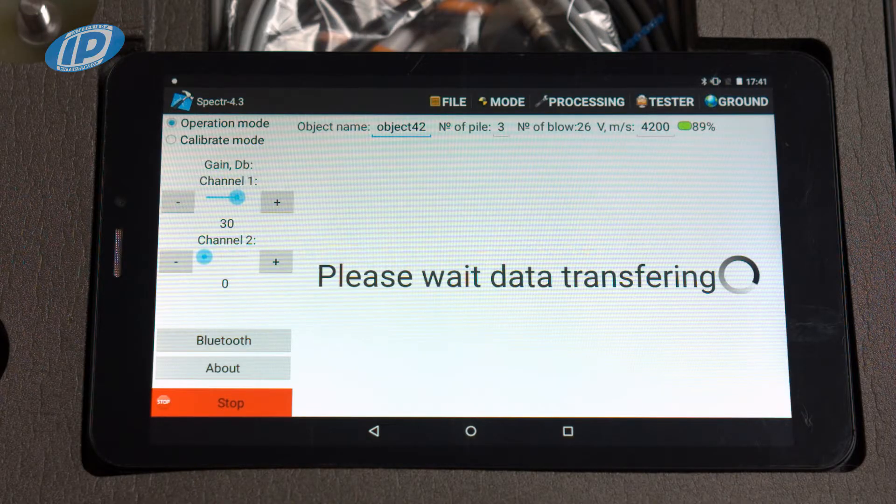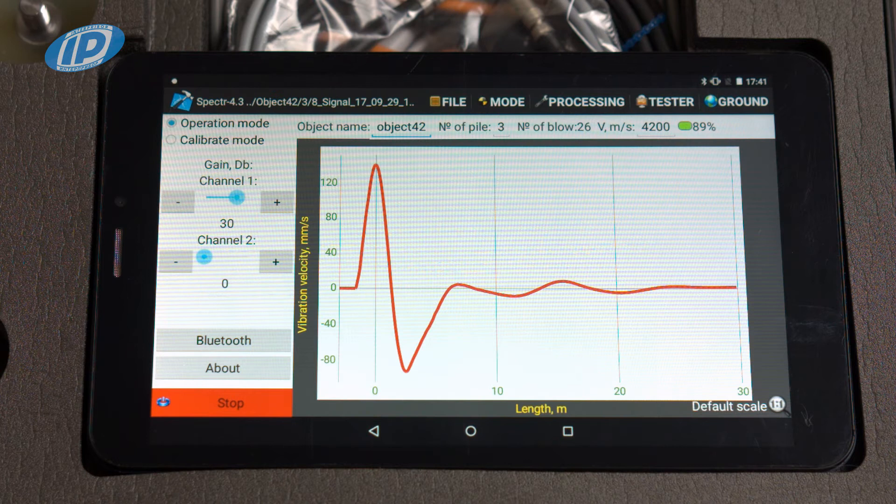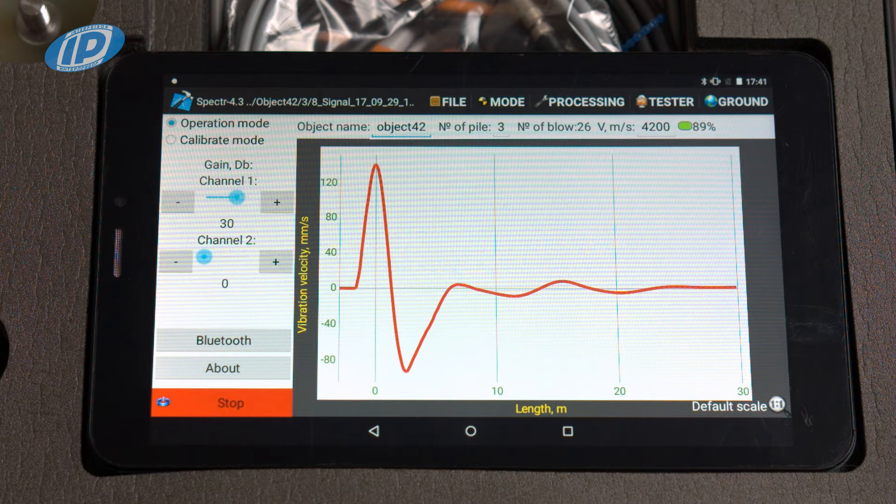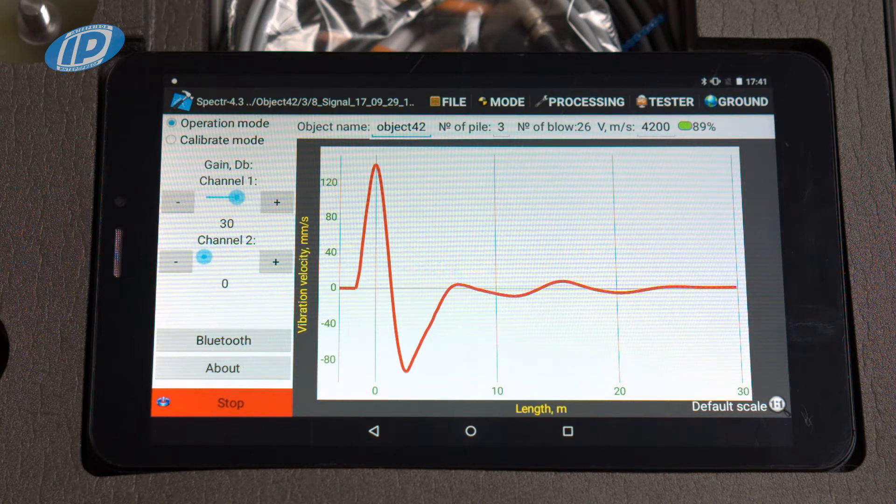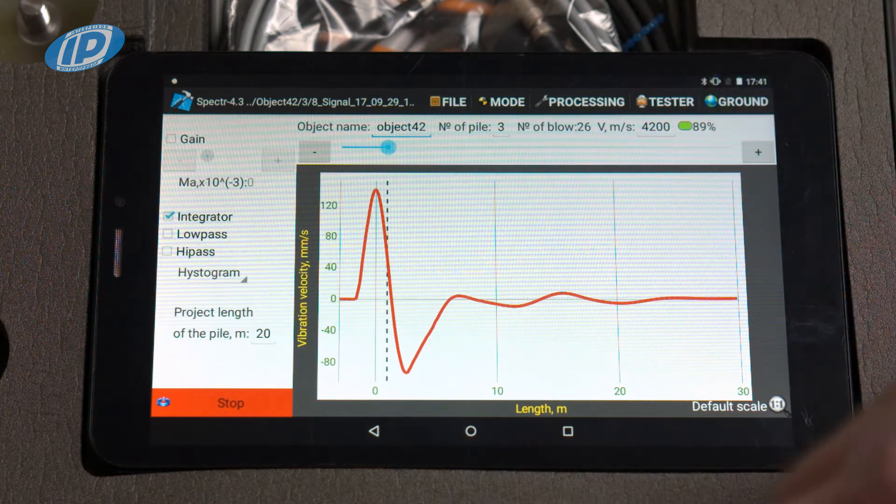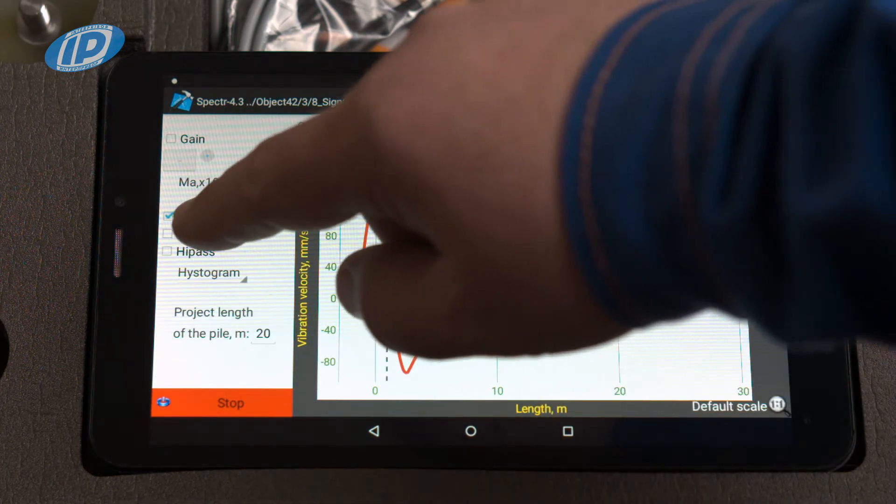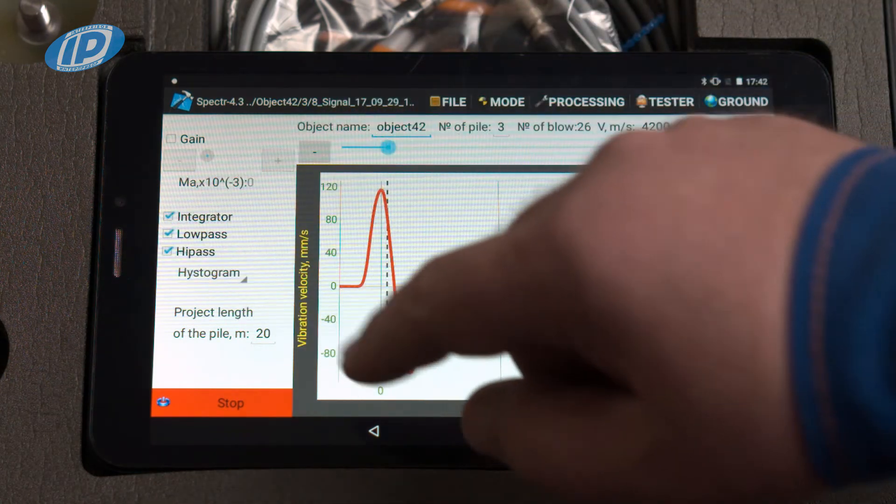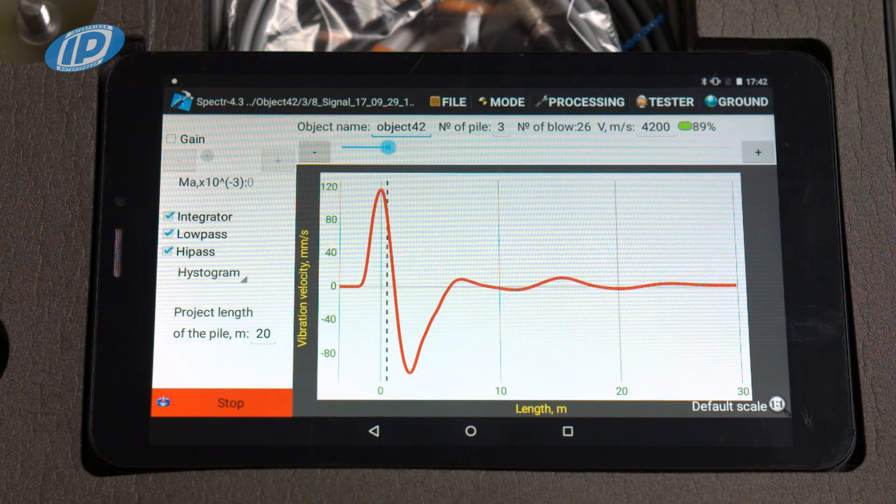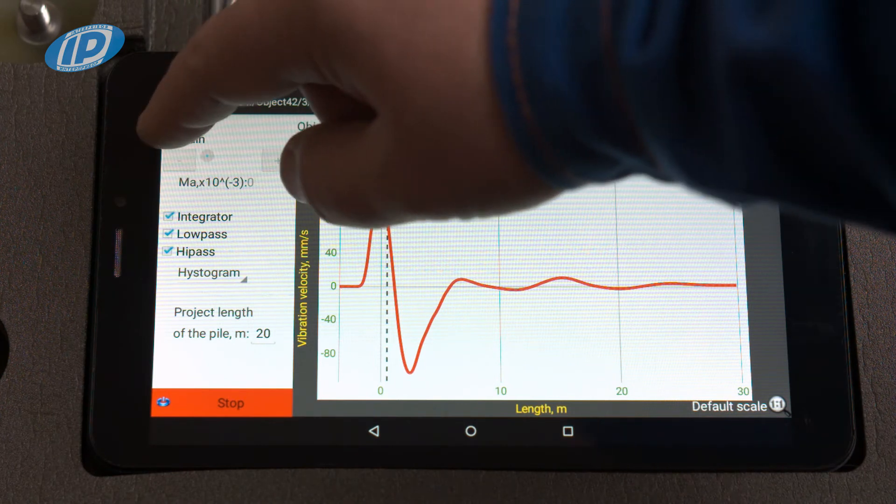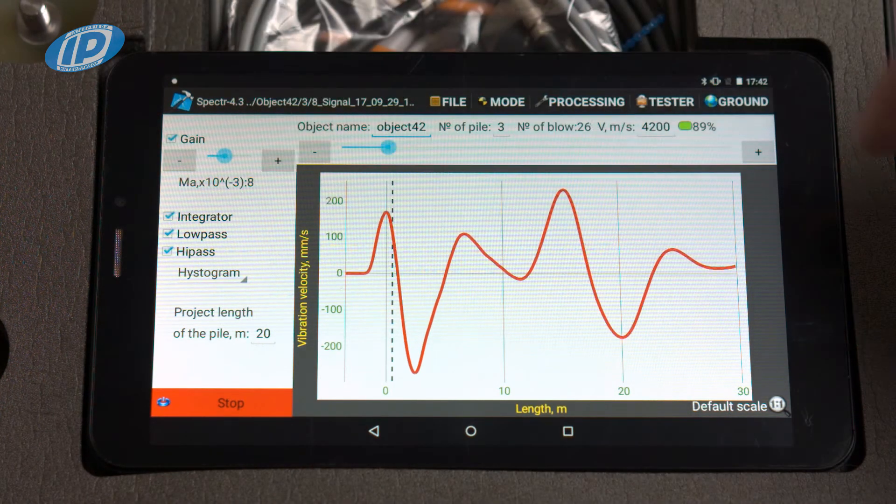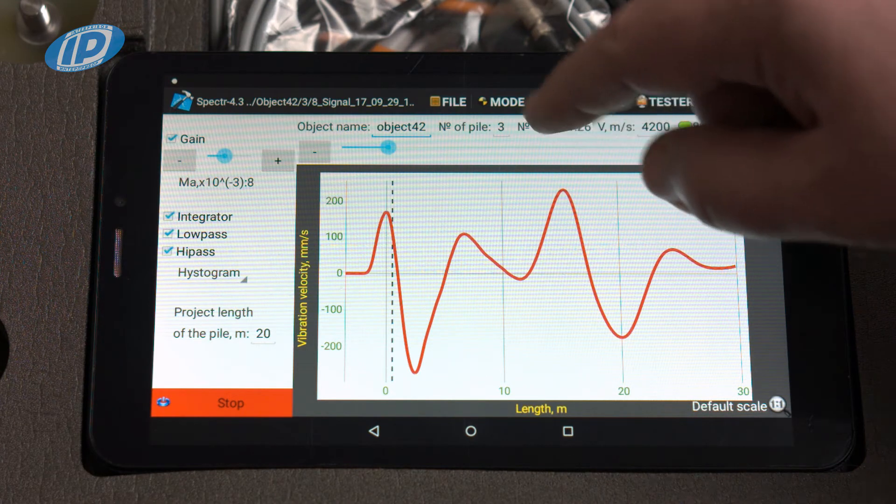After recording the signal, you can perform correction of processing parameters and signal display to facilitate its interpretation. Turn on the integrator, low and high frequency filters. Set the amplification so that the amplitude of reflection is approximately equal to the amplitude of the blow.